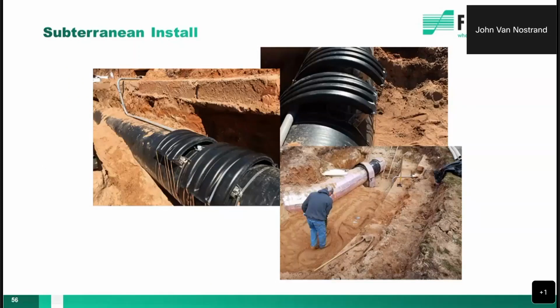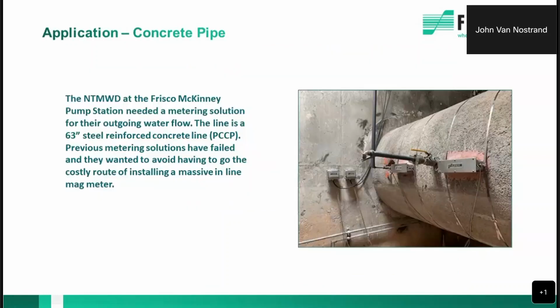So underground installations become tricky, and there are often times where you might need to put a meter in, but you don't have the ability to install a vault. So we'll bury them directly in the ground, and we'll basically prepare the transducers so that they're not going to move. We'll test the application. We know everything's working well before we backfill. Now, again, we don't necessarily like to do that, but we certainly can.